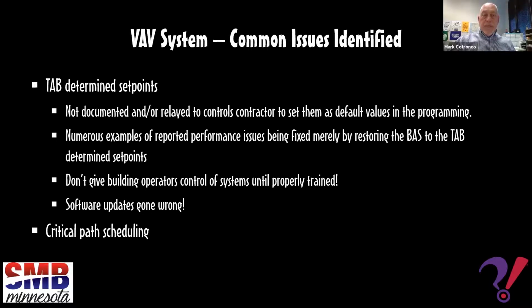Thanks, Miles. Yes, we've had some issues in the past where the control system is updated and the K factors of the VAV boxes are lost. So when that happens, the system returns to its default K factors and thus makes the system unbalanced. The calibration process then needs to be redone to get the boxes to perform per design. Boxes are kind of dumb out of the box, so they just need somebody to tell them this is what your range is. So if those K factors, along the lines of what Miles said, are actually documented, then that's an easier and faster task.